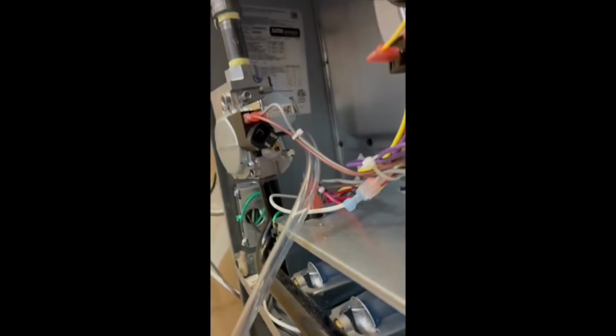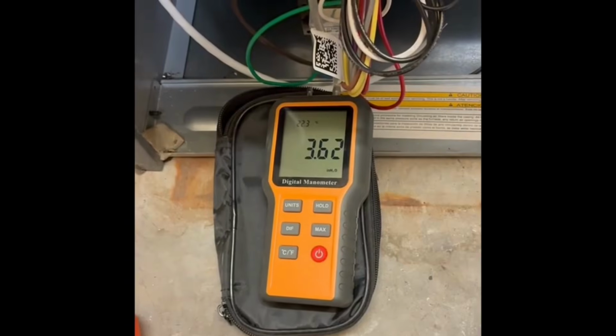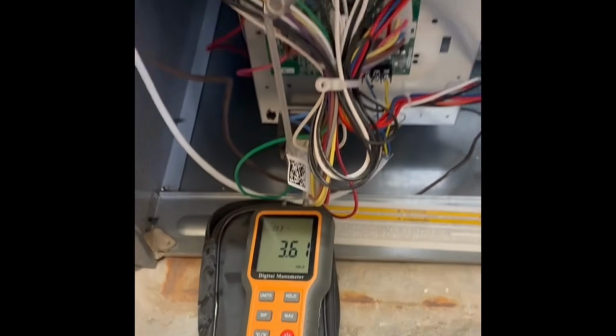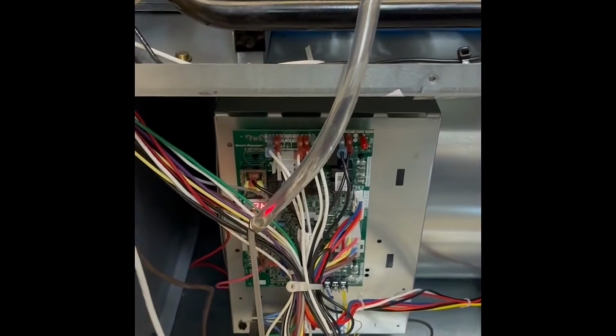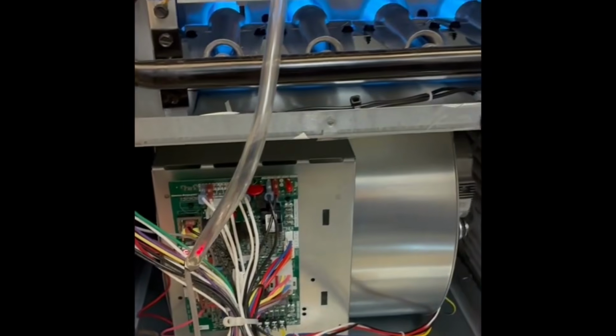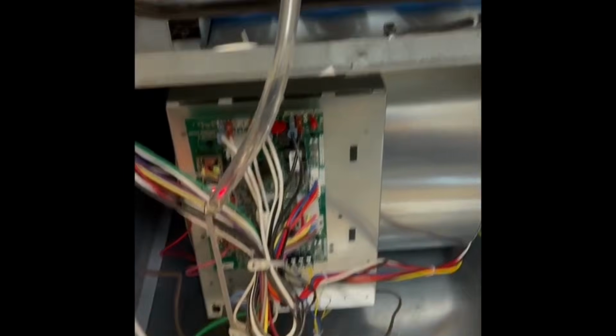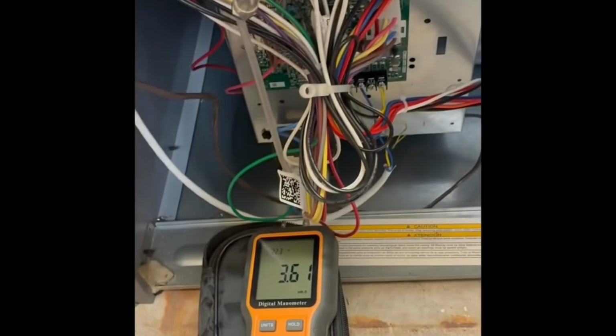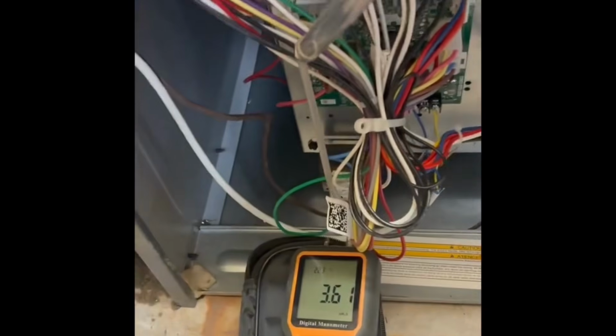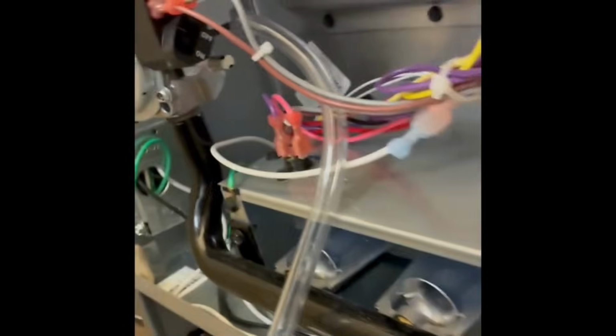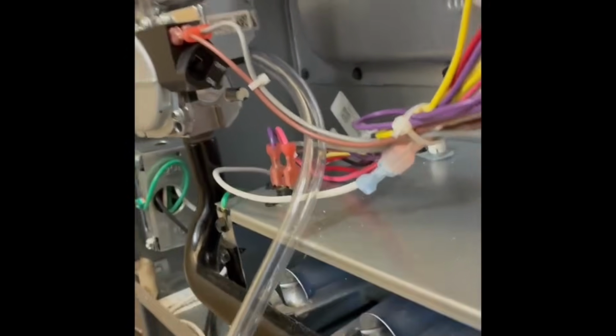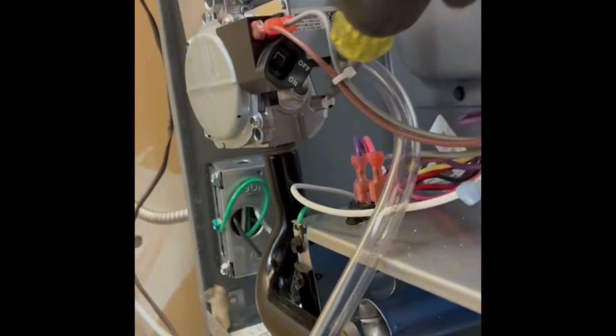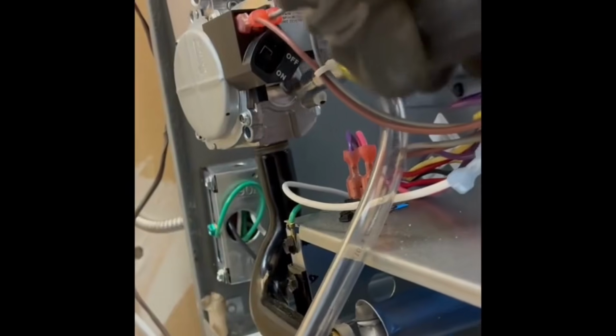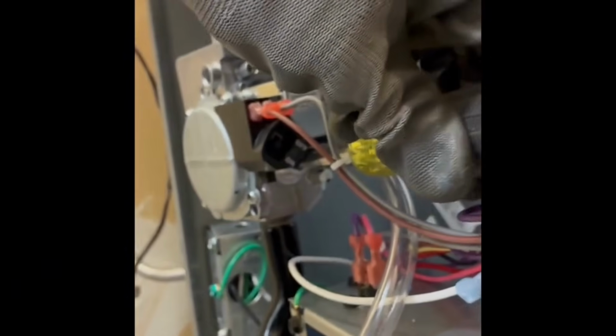What I'm going to do while it's running, we're at 3.62 is where it's settled out. So again, I want it a little bit lower. The flames look good, steady blue flames, no rollout, no lift off. So to get it to 3.5 inches of water column, I'm just going to slowly adjust this flathead screw right here. I already moved the little white plastic cover that goes over the screw. I'm just doing a quarter turn at a time roughly.